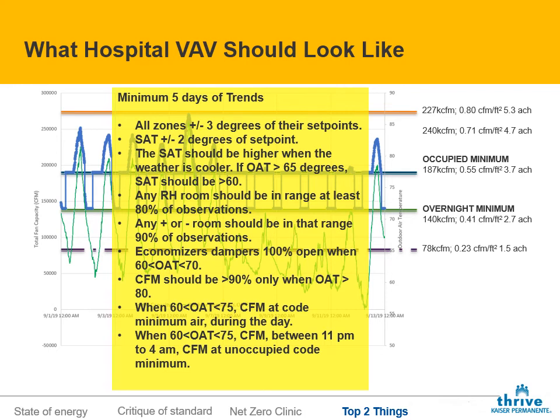Right? Economizers need to work. They should be 100% open at the right outside air conditions. Your CFM should be at 90% only when your outside air temperature is over 80 degrees. So if it's not 80 degrees outside and you're seeing your systems ramp up to the top, then something is wrong. You shouldn't accept the system. During the day, we should see our air drop down to that code minimum when the outside air temperature is reasonable. And of course, between 11 a.m. to 4 a.m., 11 p.m. to 4 a.m., when the outside air temperatures are reasonable, we should see our systems drop all the way down to that unoccupied code minimum.